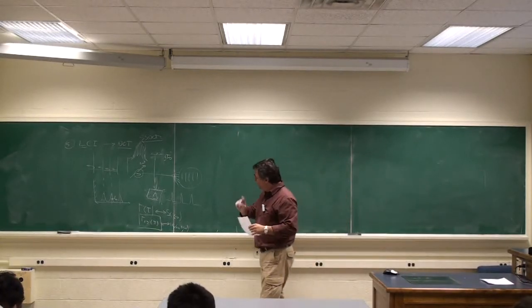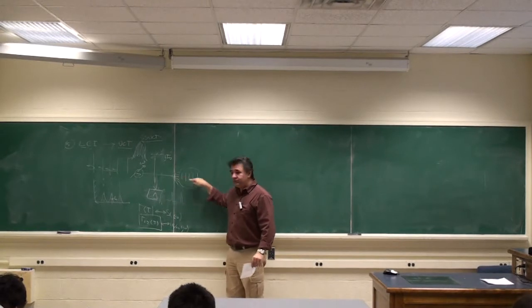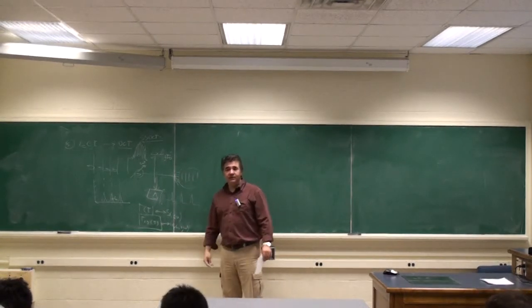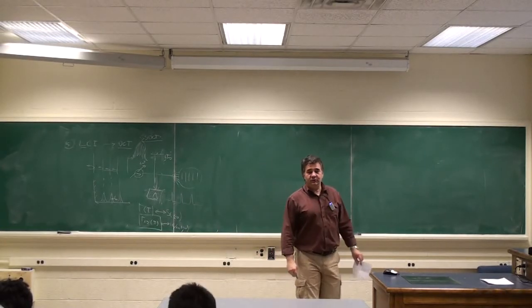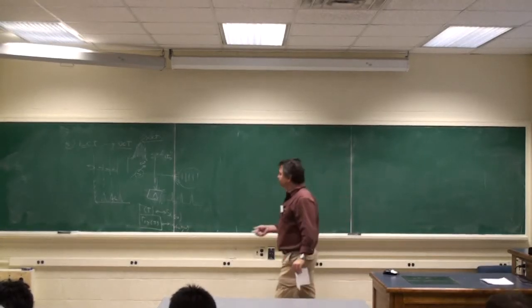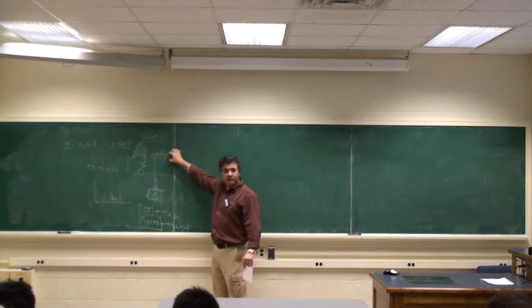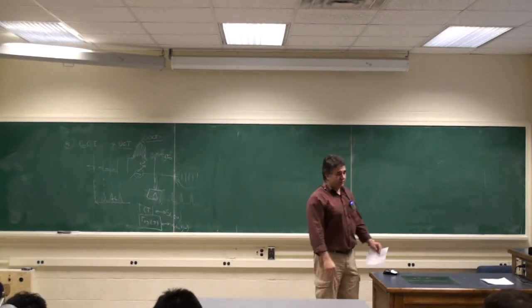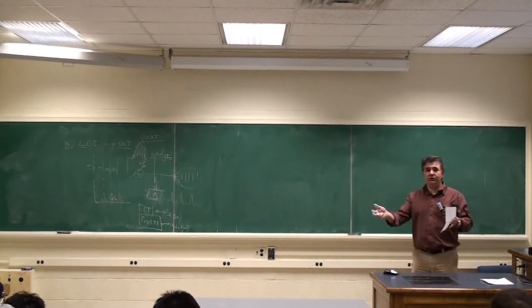Okay, so it's important in OCT to realize that this resolution, the longitudinal one, has nothing to do with the numerical aperture, right? It's the coherence time, the coherence length. So that makes it special. While the resolution in a microscope, right, it's all about the numerical aperture.